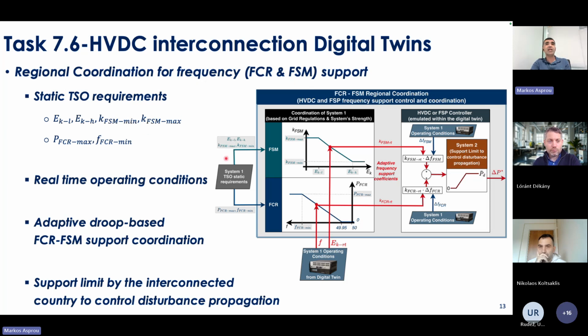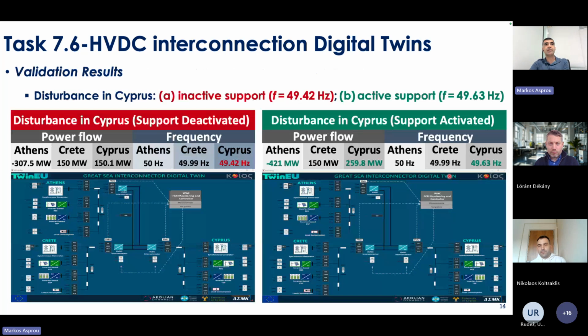The TSO imports the requirement for inertia and FCR, and according to the real-time operation of the system, the gains for the FCR and FSM are determined through this coordination scheme. The power that should be provided by the HVDC to support the grid under a frequency band is determined through this condition.